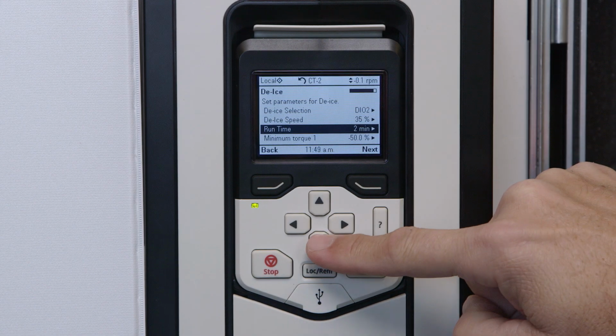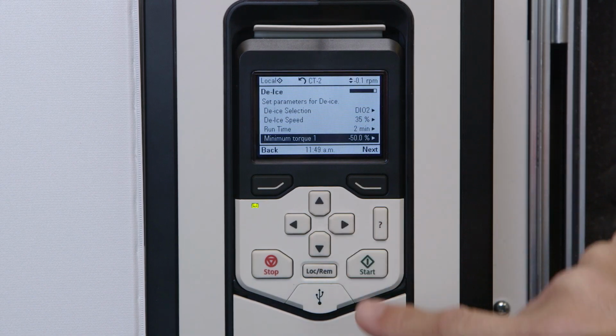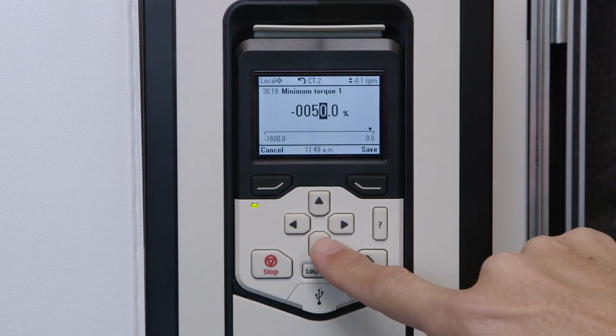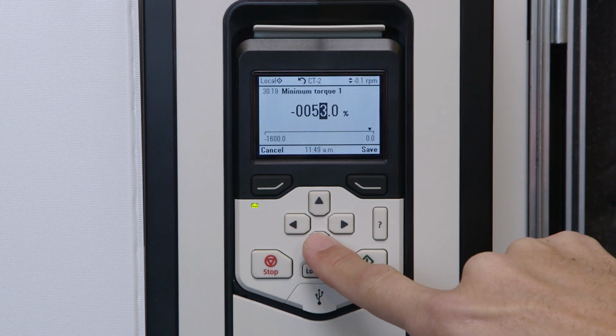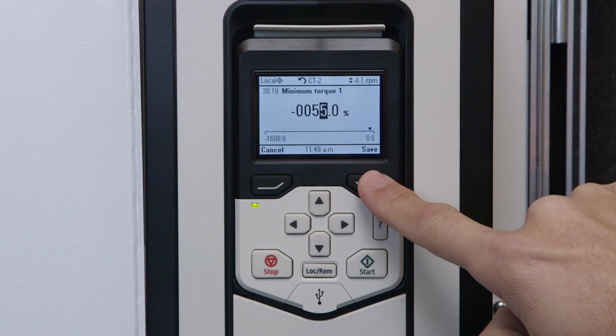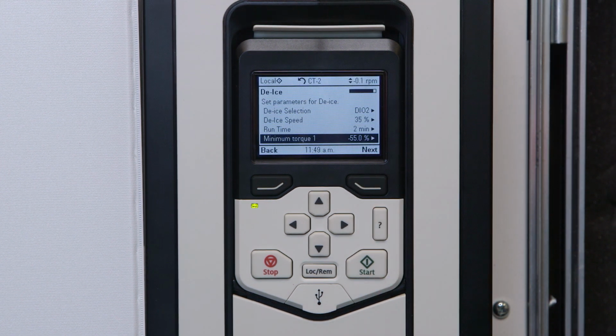Ensure the minimum torque setting is negative. The minimum torque default is minus 50% because the fan will be rotating backwards. Once this data is entered, press Next.